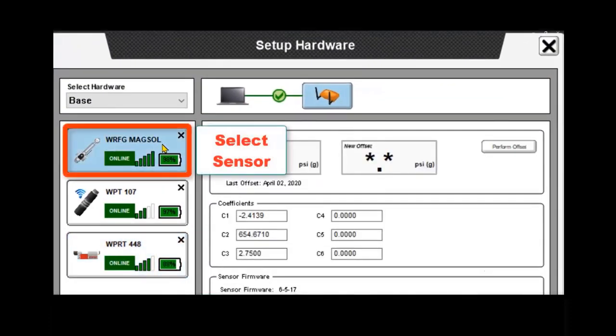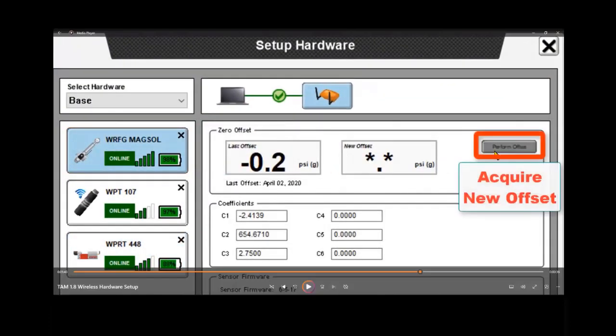Here you can see we've selected our sensor. There is no pressure on the sensor at this time. If you zero the sensor with pressure on it, it won't mess up the data, but it will mess up the zero offset on the pressure transducer.